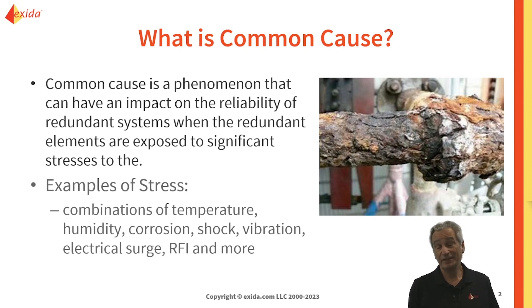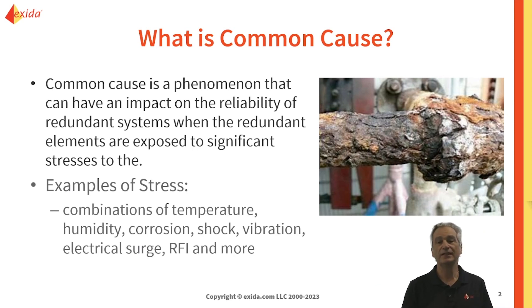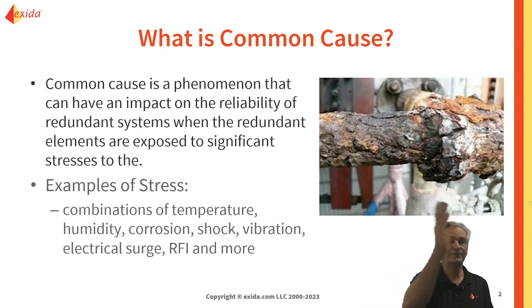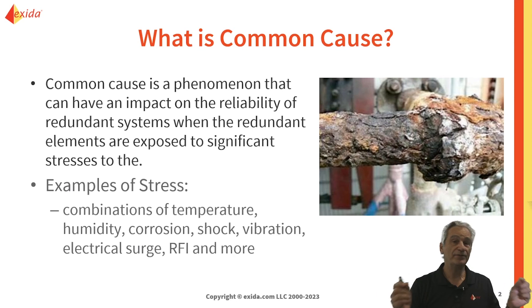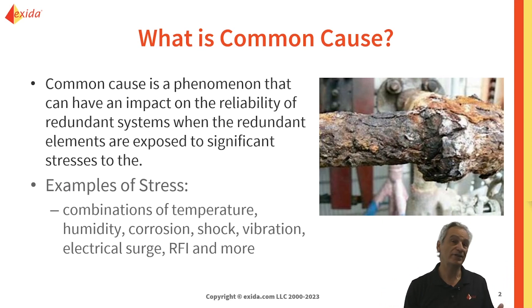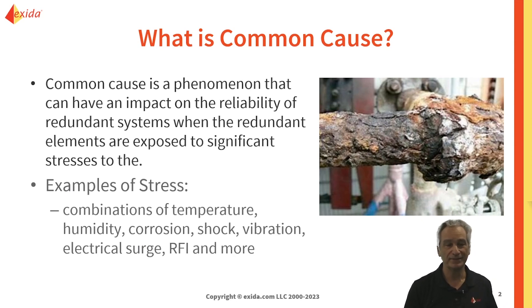There's another extreme example. There was actually a case where a forklift driver was running through part of the plant where they had conduit overhead, and he had his fork up too high and hadn't realized, and he actually took out the conduit. Unfortunately for the plant, they had both sets of redundant cables for their systems running through the same conduit. So in one fell swoop, he took out the whole redundant system.